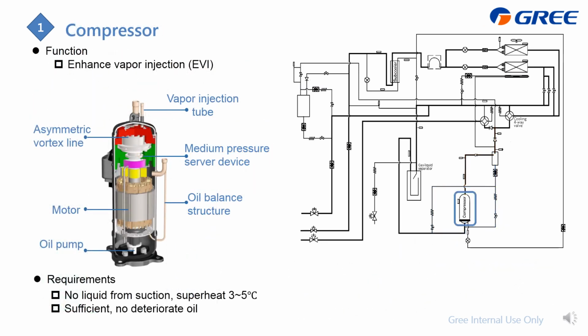Now the most important part, the compressor. This one is from Hitachi, the same as the GMV5. Also, it is a scroll, but this one has EVI, which is short for enhanced vapor injection, which is very helpful in low temperature heating. And here is how we inject the refrigerant in heating mode. Also, from here, it is the liquid and a partial refrigerant. We get through this EXV, and then at this subcooler, the refrigerant will become gas. And then we inject this gas into the compressor.